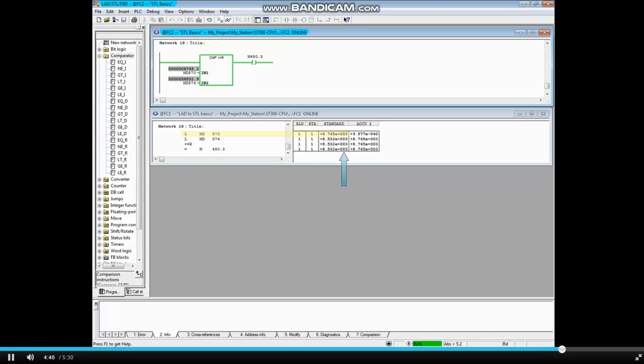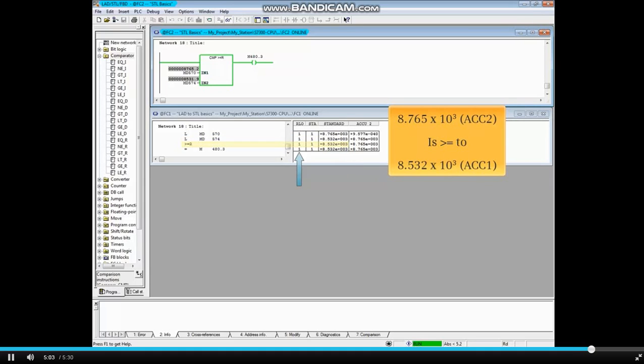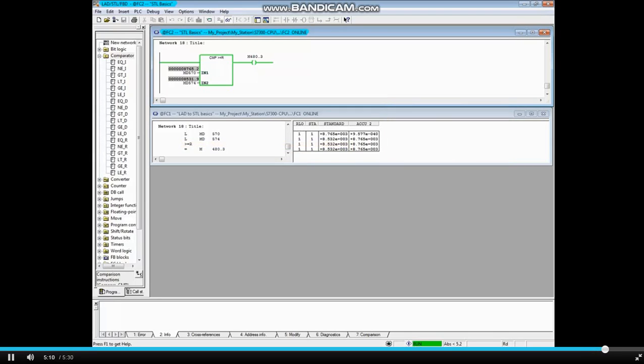MD570's value is the same as before, but memory double word 574's value has decreased to 8.532 times 10 to the third power. The greater-than-or-equals-to as real numbers instruction is now true because the first number is larger than the second. As a result, the status of coil M480.3 is also true. This concludes the video on STL comparisons.